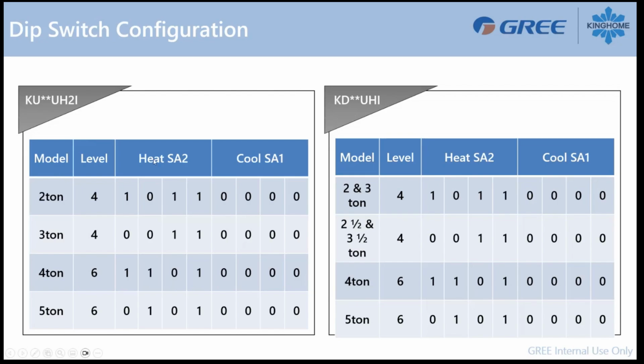Because we're using different tonnage, there's different configuration. So if you're using a 2-ton, you will see here a bunch of 1 and 0. 0 means on, so position on. 1 means off. So basically for a 2-ton unit, you will see off, on, off, off, on. Okay, those SA1 configurations here are always in the on position for both air handlers.